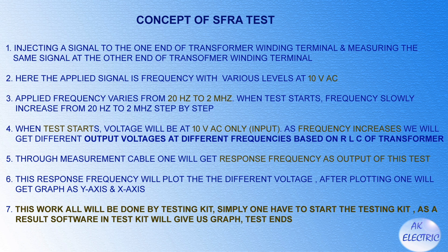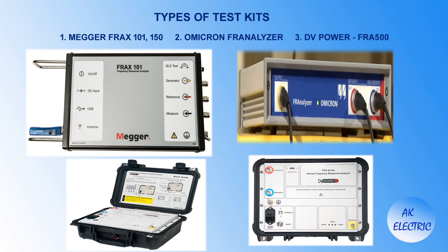All this work is done by the testing kit. One simply starts the testing kit, and the software in the test kit will produce the test graph as a result. The three testing kits most widely used for SFRA test are: Megger FRAX 101, 150 series, Omicron, and DV Power FRA 500.